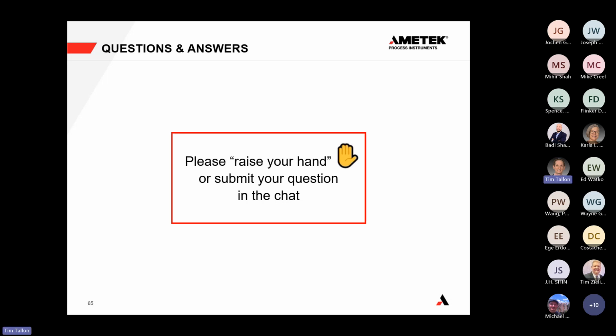So I appreciate CEMS measurements. They're absolutely important, especially from the stack perspective. Before we release emissions, it's really important to have visibility on that for emission monitoring and for regulatory compliance. When it comes to monitoring the combustion firebox in real time, that's where I think about having a flue gas analyzer right outside the radiant section. So if it's a fired heater, right outside the radiant section.